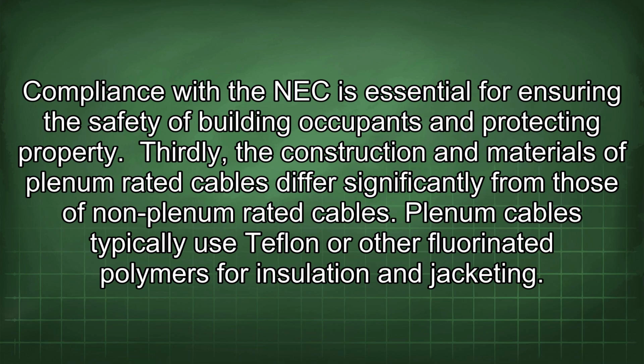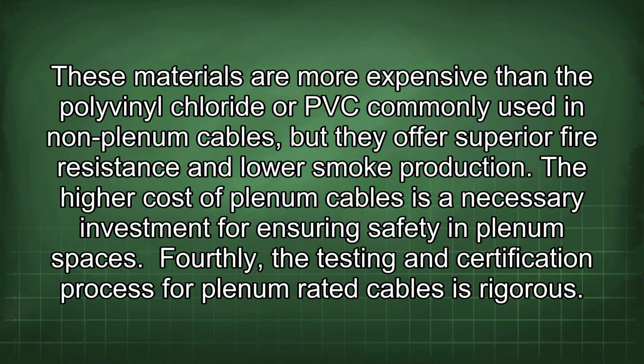Thirdly, the construction and materials of plenum-rated cables differ significantly from those of non-plenum-rated cables. Plenum cables typically use Teflon or other fluorinated polymers for insulation and jacketing. These materials are more expensive than the polyvinyl chloride, or PVC, commonly used in non-plenum cables, but they offer superior fire resistance and lower smoke production. The high cost of plenum cables is a necessary investment for ensuring safety in plenum spaces.